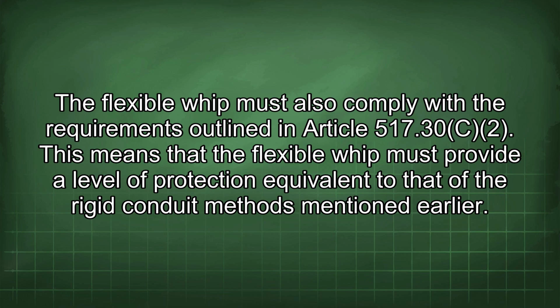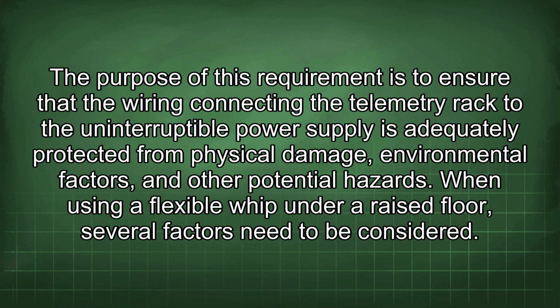The flexible whip must also comply with the requirements outlined in Article 517.30(C)(2). This means that the flexible whip must provide a level of protection equivalent to that of the rigid conduit methods mentioned earlier. The purpose of this requirement is to ensure that the wiring connecting the telemetry rack to the uninterruptible power supply is adequately protected from physical damage, environmental factors, and other potential hazards.